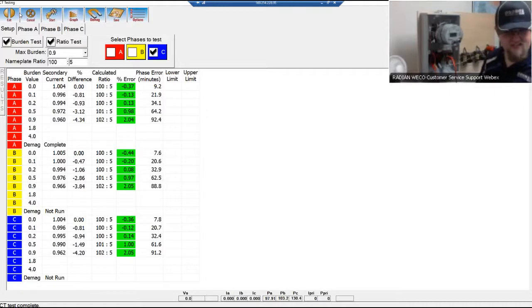So single phase CT testing, that can be used for a 3-phase application. So the Bantam Plus is slightly different than the RW in terms of you have to put your hands in here just a little bit more to get each phase tested, but will allow you to do 3-phase CT testing on your Bantam. And then same thing with the primary as well. We would hook up to each one that we're doing. So if I was testing A phase, I can hook up to A phase, run the test, hook up to B, run that test, C, run that test. We move the duckbill and the primary probe right alongside each one.